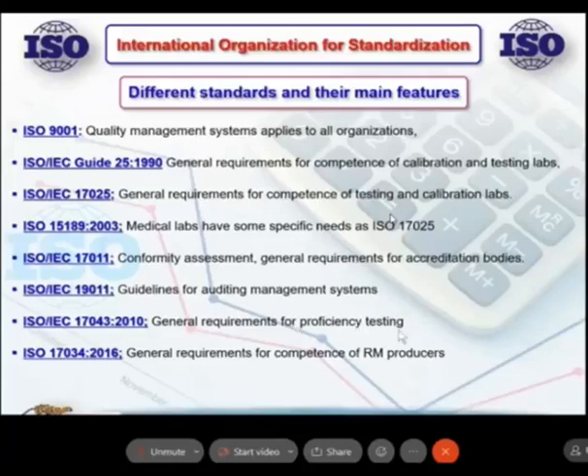If your lab, say in Aramco, SABIC, or any lab, wants to be a PT provider, it's okay. Prepare your sample, split it and distribute it all around the world. But before you start, you have to get approval from the ISO organization. This approval is the 17043 certificate. So when your lab goes for accreditation for ISO 17025, you have to participate in international proficiency tests provided by an organization around the world that has a 17043 certificate. Okay.